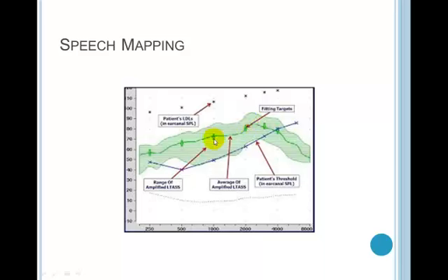These little, they're actually T's, but that's the green. Way up here, the asterisks are the predicted uncomfortable levels of that patient, or if you obtain those levels, you can put them in. Then what happens is, while the hearing aid is in place and all of these things are on, you click a button and there's running speech. For example, if any of you have seen this, there's a man telling a story about how carrots are grown.